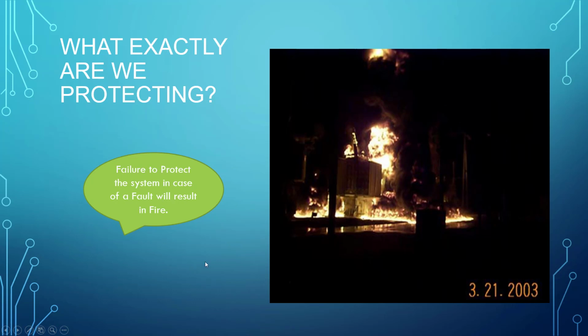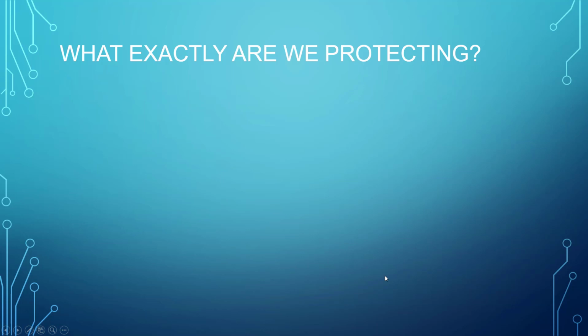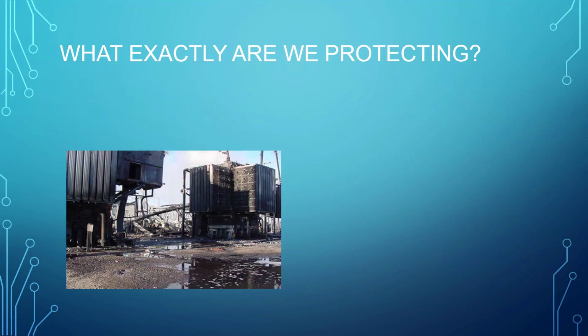As we can see in the picture, this is fire caused by a short circuit, which is a result of a protective system that failed to react in time. Even so, when this happens, you still need to have a system in place that will isolate this particular transformer, which is on fire, from the other equipment, so that you can minimize the damage only to this particular equipment. We are protecting these local installations of your substation. As you can see, this is the aftermath of a fire that has just unraveled an entire substation. You don't want that to happen.